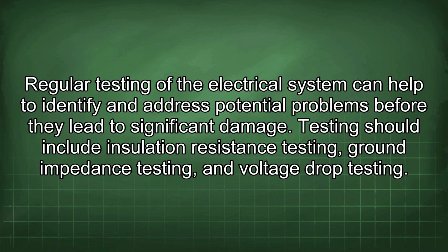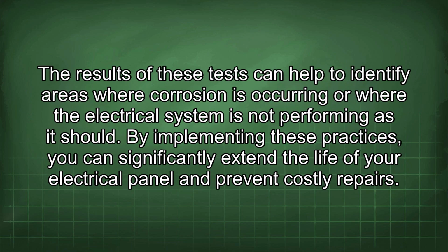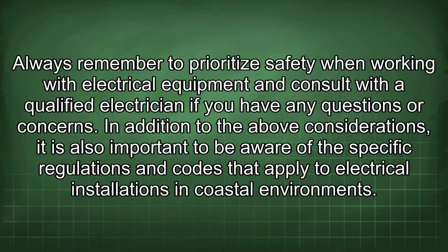Regular testing of the electrical system can help to identify and address potential problems before they lead to significant damage. Testing should include insulation resistance testing, ground impedance testing, and voltage drop testing. The results of these tests can help to identify areas where corrosion is occurring or where the electrical system is not performing as it should. By implementing these practices, you can significantly extend the life of your electrical panel and prevent costly repairs. Always remember to prioritize safety when working with electrical equipment and consult with a qualified electrician if you have any questions or concerns.